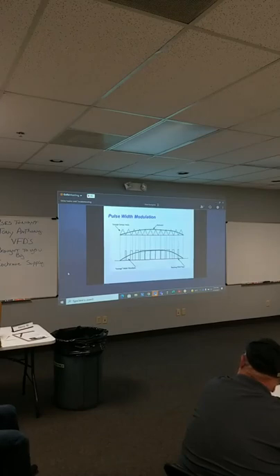Because what sometimes will happen is the insulation of that motor can't take that extra peak-to-peak voltage, which creates more heat. And usually at the first turn, right when the windings come in, they make that hard 90, that's usually where they'll fail first. And that motor may last a week, it may last a few years, there's no way to know. But I recommend that they make sure they have an inverter rated motor, where the insulation between the windings is designed to handle that extra heat, because we're pulsing DC out to that motor.